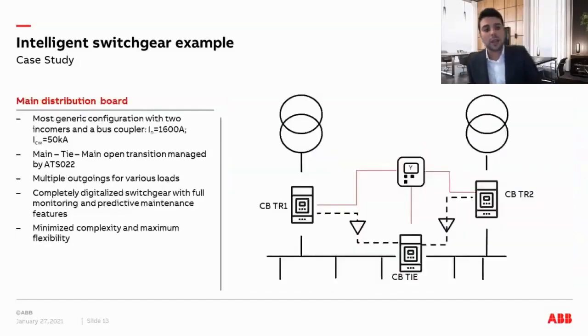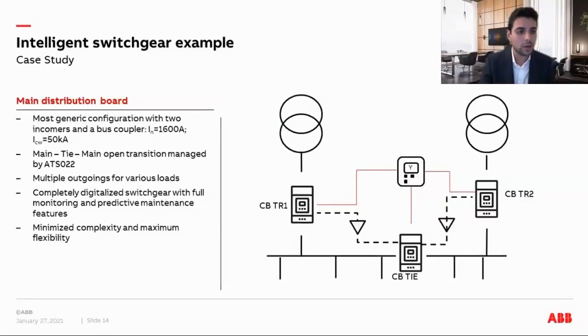Our intelligent switchgear example is for the main distribution board of low voltage distribution. In our case, we realized a generic configuration having two incomers and a bus tie coupler. The rated current is 1,600 amps with ICW short circuit current rating of 50 kiloamps.